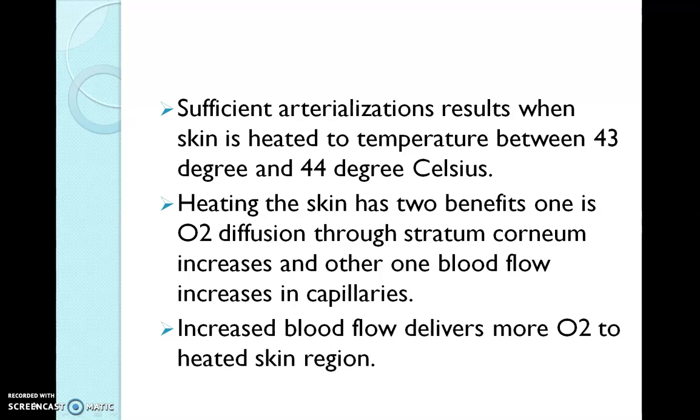Heating the skin has two beneficial effects. Oxygen diffusion through the stratum corneum increases, and vasodilation of the dermal capillaries increases blood flow to the skin at the sensor site, where the heat is applied. Increased blood flow delivers more oxygen to the heated skin region, making the excess O2 diffuse through the skin more easily.